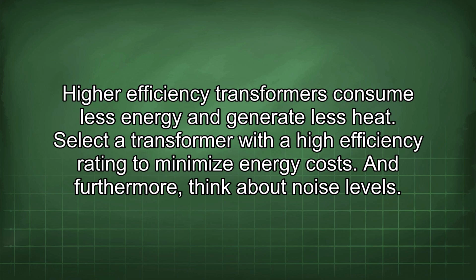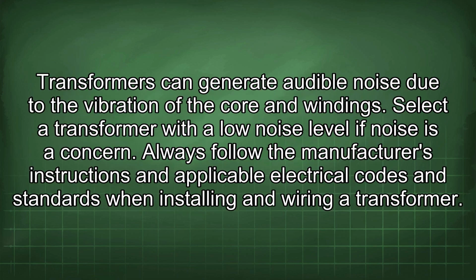And furthermore, think about noise levels. Transformers can generate audible noise due to the vibration of the core and windings. Select a transformer with a low noise level if noise is a concern.